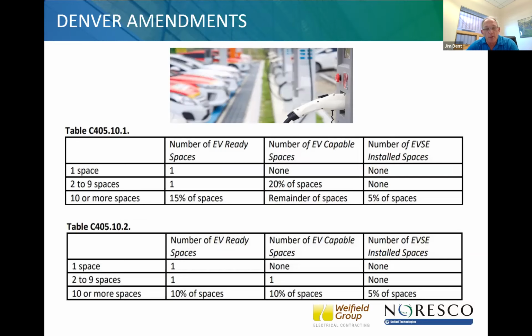Next slide, Kevin. So C405.10.1 is the residential table. And you'll notice that for 10 or more spaces, 15% of the spaces have to have circuits pulled to them. They are EV ready. The remainder of the spaces have to be EV capable, and 5% of the spaces actually have to have charging equipment installed. And in all cases, when you do these calculations, you're required to round up in terms of the number of spaces. Table C405.10.2 is for office buildings. And you'll see for office buildings, 10% of them have to be EV ready with circuits pulled to them. 10% have to be EV capable with empty conduits, but no panel or anything. And then 5% of the spaces have to have EV charging equipment installed.